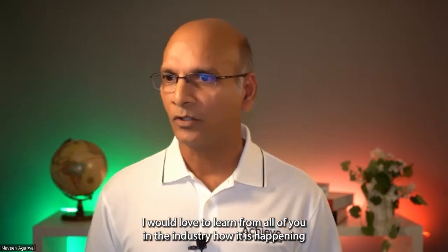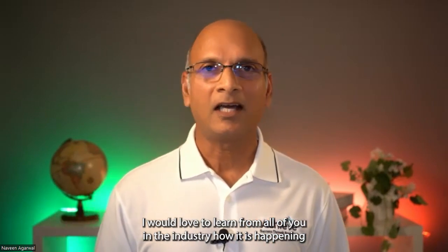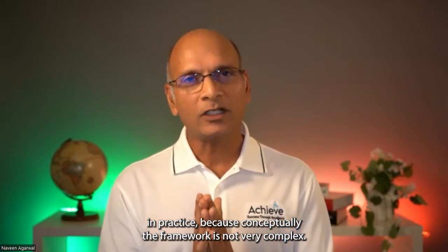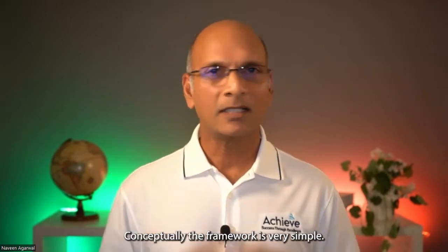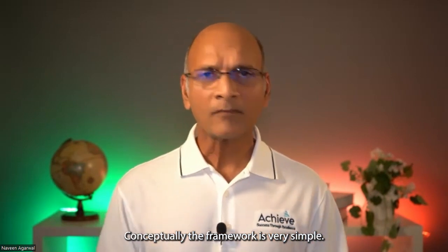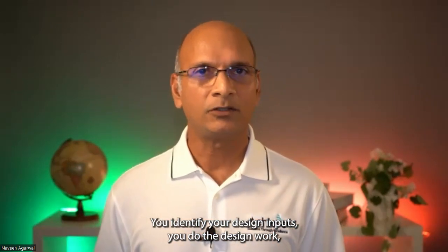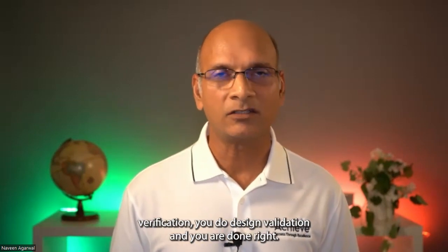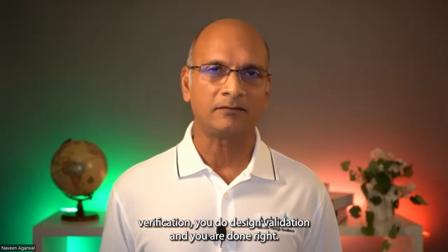I would love to learn from all of you in the industry how it is happening in practice. Because conceptually, the framework is not very complex. Conceptually, the framework is very simple. You identify your design inputs, you do the design work, you get to the design outputs, you do design verification, you do design validation, and you're done, right?